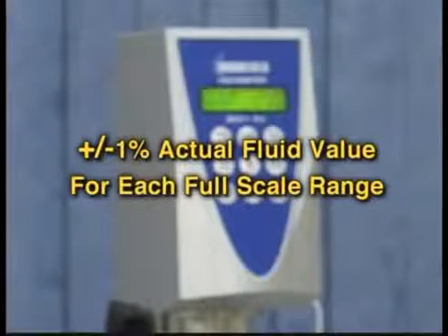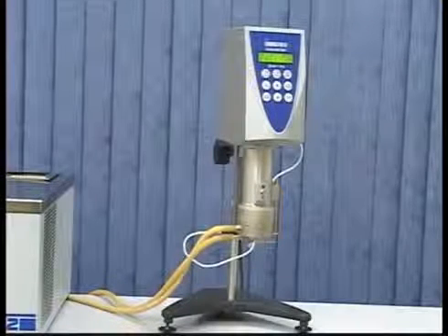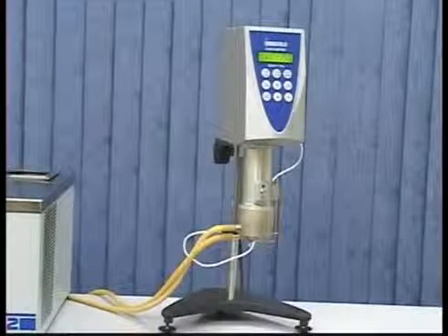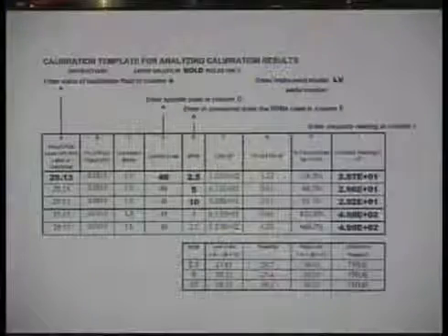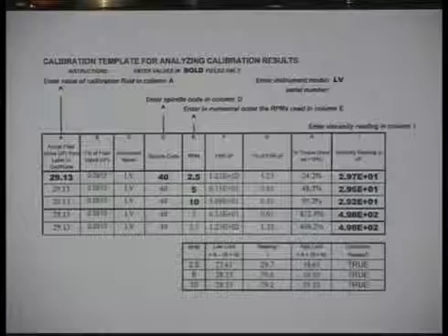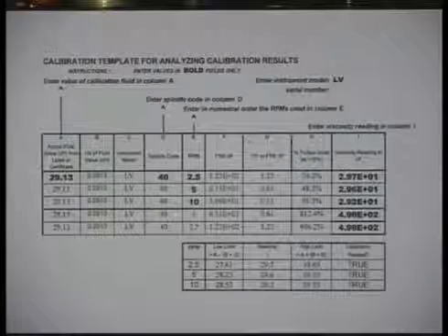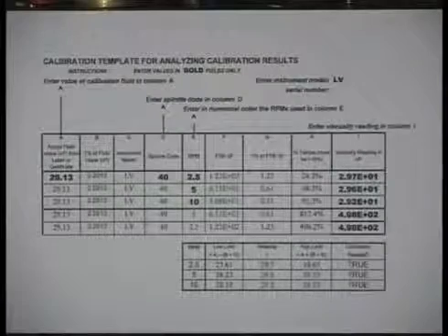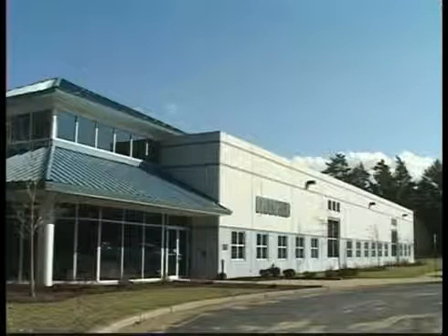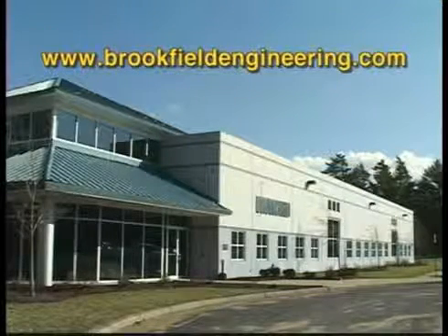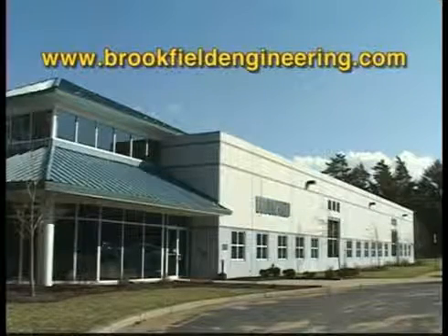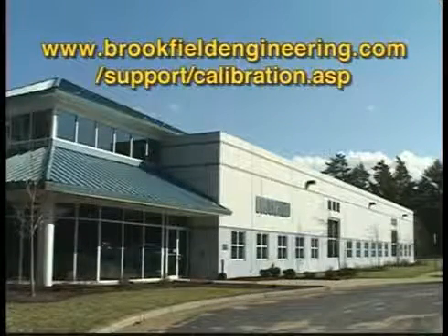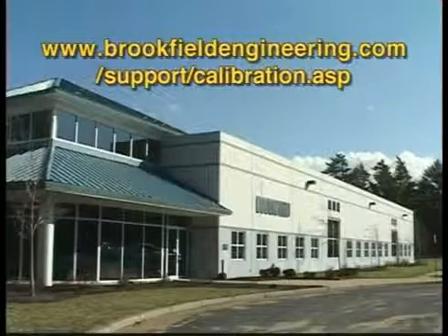Tolerances for calibration are computed using plus or minus 1% of the actual fluid value for each full-scale range. You can perform a calibration check manually and enter the values and compute the tolerances for pass-fail criteria. Brookfield supplies a calibration worksheet on our website that easily allows you to enter data, computes the tolerances for each range, and gives pass-fail criteria automatically. You can download the calibration worksheet from Brookfield's website at www.brookfieldengineering.com. Going to the link on your screen will take you directly to the calibration worksheet.